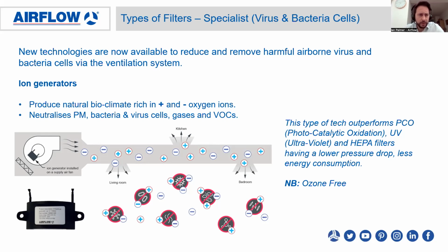The ion generators produce a natural bioclimate rich in positive and negative oxygen ions, and they neutralize particulate matter, bacteria and virus cells, gases and VOCs. So this type of technology actually outperforms PCO, photocatalytic oxidization, and UV, ultraviolet, and HEPA filters, because they have a lower pressure drop and less energy consumption. And they're also ozone free.